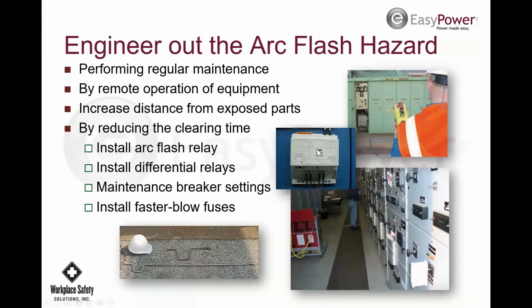This is a great tool. It's an arc flash relay. The fiber optics will run all through the switchgear, and then there are contacts, and this might be connected to two separate breakers. One might be a main breaker here, another one might be a tie breaker on this side. It goes to the shunt trip of these breakers, and it'll trip them so fast that it brings the arc flash way down. And it doesn't mess up coordination, which is the real beauty of this. It just makes the trip time a lot faster and doesn't screw up anything else.